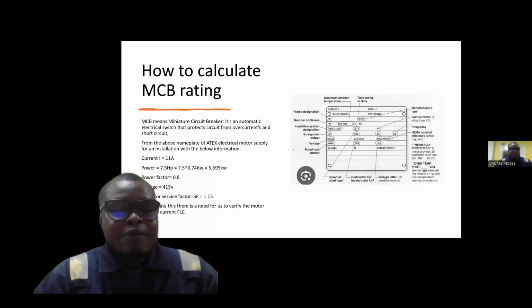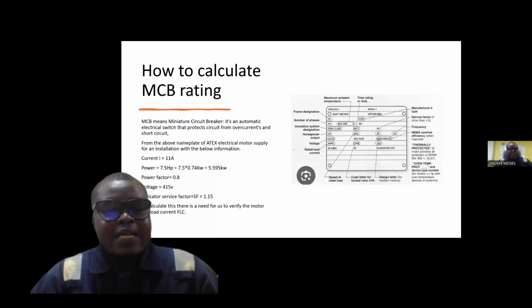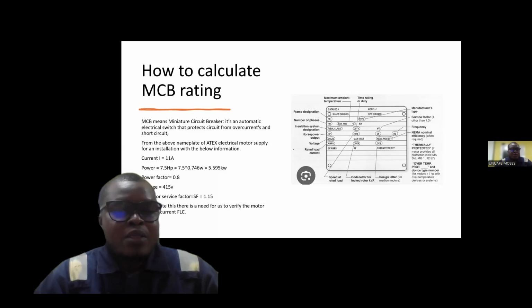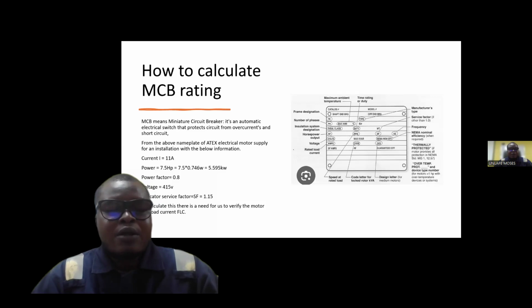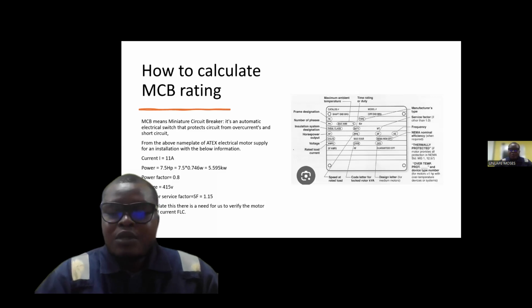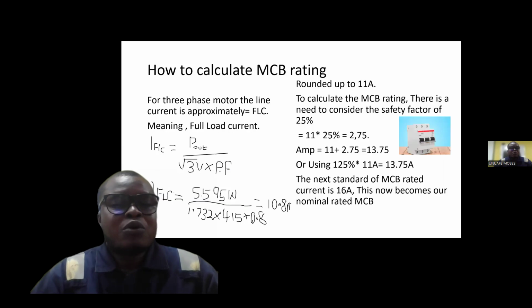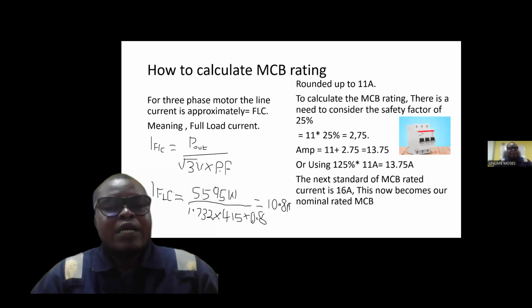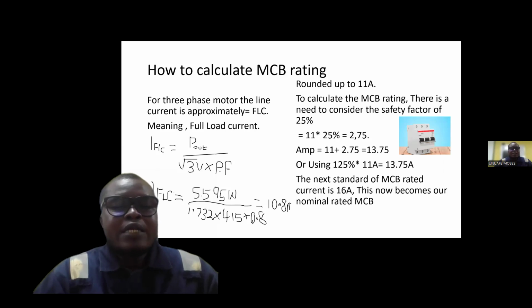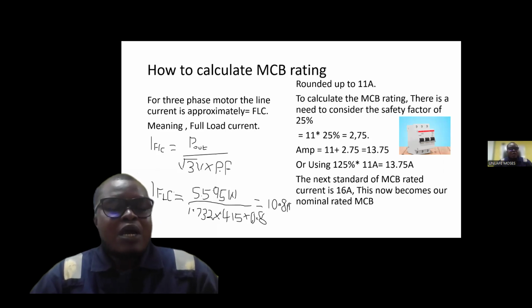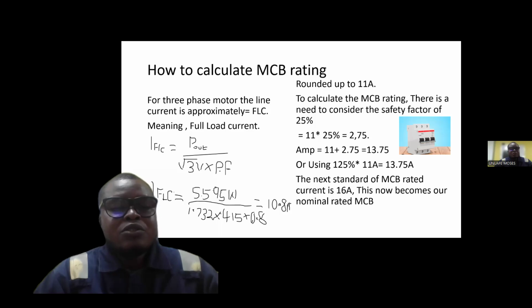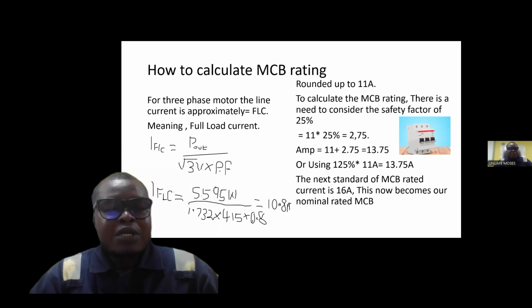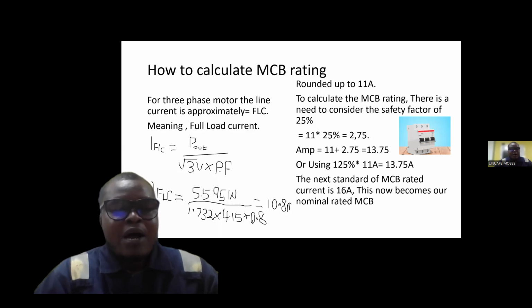The indicated service factor, regarded as SF, is 1.15. Now, for us to calculate, there is a need for us to verify the motor's full load current. To verify the full load current, we have to apply the formula for a three-phase motor current. We have our full load current formula to be P, which is the power output, all over root of 3 multiplied by voltage times the power factor.